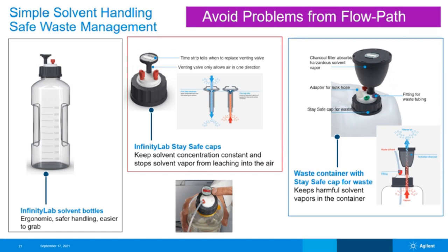The Stay Safe caps prevent solvent evaporation, which is great for those organic solvents that do sit on your system for some time. Organic solvents and some additives are volatile, affecting the percent composition. Sometimes even a small change in composition can affect your separation, so it's best to be safe here. The Stay Safe caps can also be used on the waste can to avoid any solvent evaporation. InfinityLab Stay Safe caps have a handy time strip that will tell you when to change the filter, approximately every 6 months, depending on the solvent and the use.